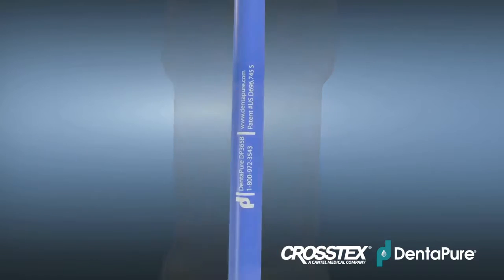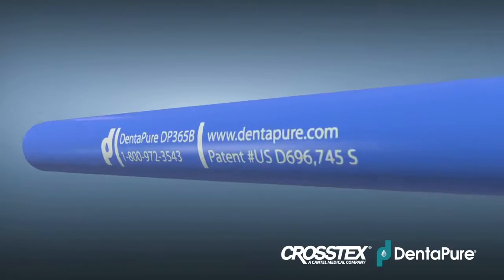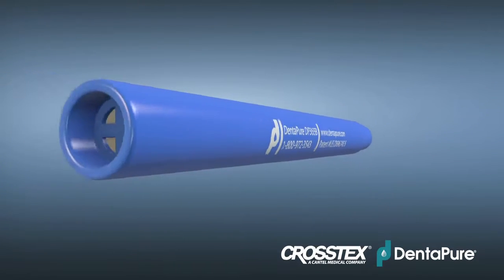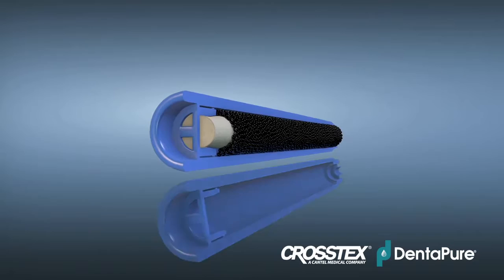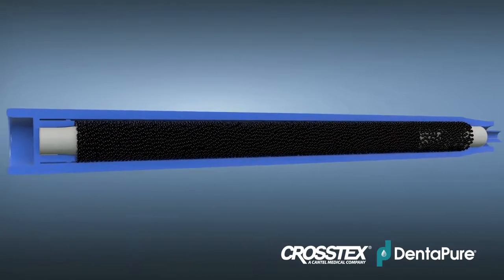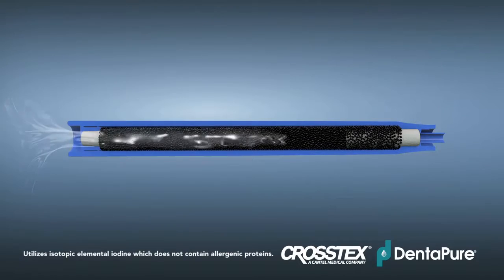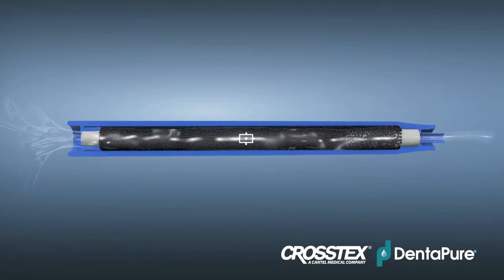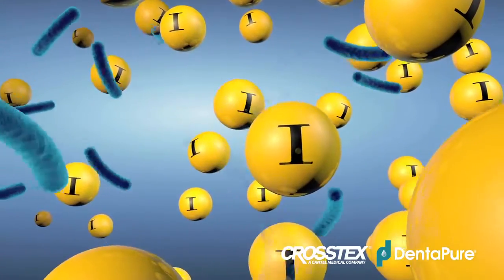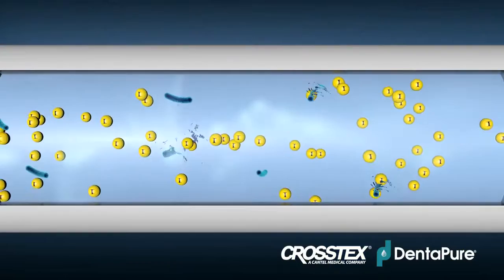DentaPure meets or exceeds all these agency guidelines. It's essentially rocket science for water, using the same resin bead technology developed for NASA to ensure the safety of water consumed in space. The DentaPure cartridge contains iodinated resin beads. As water passes through, the resin releases two to four parts per million of atomic iodine isotopes, controlling bacteria and keeping your dental unit water safe for an entire year.